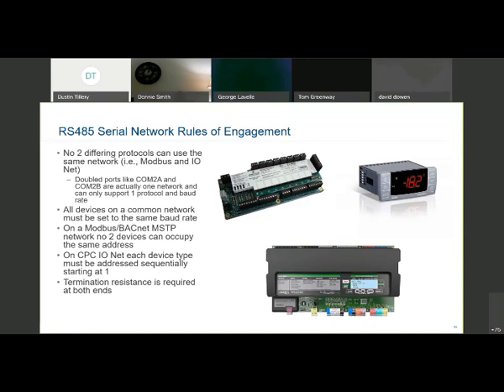That being said, the baud rates also have to be set the same. Okay, baud rate again is the speed at which those devices communicate back to the E2. So we cannot have, let's say, an I/O net device plugged into COM2 set for 9600 baud rate, and another I/O device on that same comm loop set for 19.2. The 2 devices would not communicate back to the E2 due to the conflict in the baud rate.